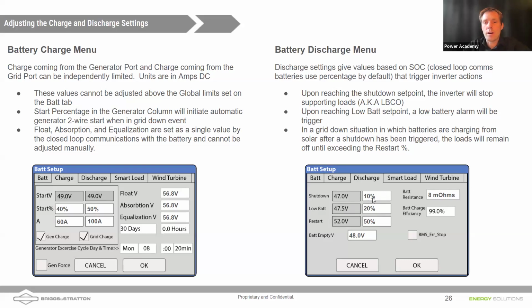The 10% value here at shutdown would be our end. That's what the shutdown here is going to shut the loads off from the inverter. So if your battery gets that low and you don't have any charging source that's capable of providing power, it'll actually shut the loads off. It'll shut the loads off until either grid comes back or solar comes out. And if there is no grid and we're coming back with solar, it's going to allow those batteries to charge all the way up to the restart value here. That's that 50% before turning loads back on. So you could set that a little bit lower. That gives the batteries a chance to get up to speed and solar to get stronger before it turns loads back on.